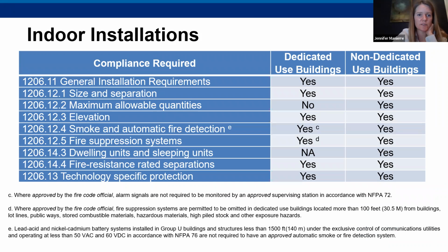This chart shows the different requirements that either apply or don't apply based on whether or not it's a dedicated use building. A whole lot of yeses in both columns here. The one that sticks out as a no is the maximum allowable quantities. I teed that up a little bit earlier on a previous slide. Dedicated use buildings are not subject to the maximum allowable quantities requirement. They can have more. Other than that, they pretty much all have to follow all of these things: the size and separation requirements, the elevation requirements, smoke and fire detection, fire suppression, etc.